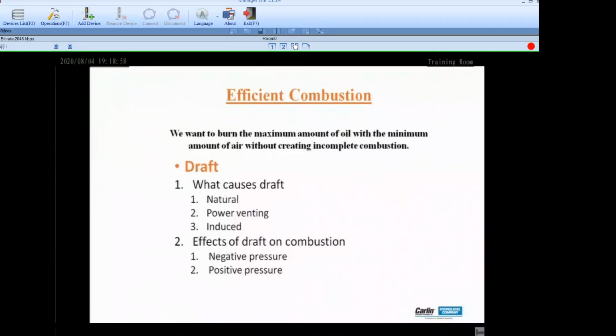Negative pressure, positive pressure. Most technicians understand negative pressure, negative draft over the fire, negative draft at the breech. You know what you've got, very easy to conceptualize. But positive pressure is not always well understood. Many technicians feel that equipment operates better against negative draft and not positive draft, not fully understanding that some setups are designed for positive draft and they will fire better under positive pressure. So it is important that we explore negative and positive pressure applications, that we understand the difference and know why they exist.